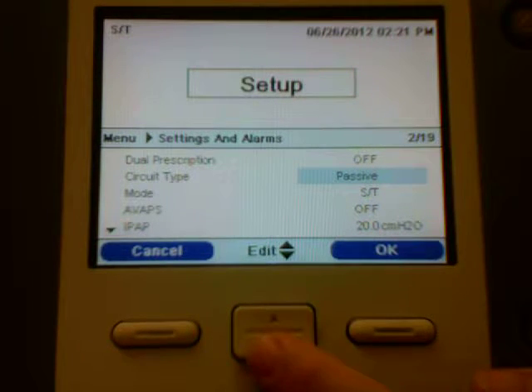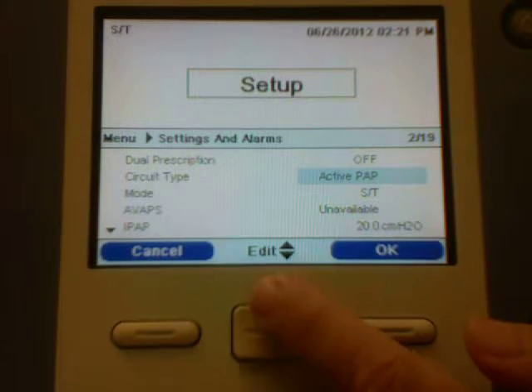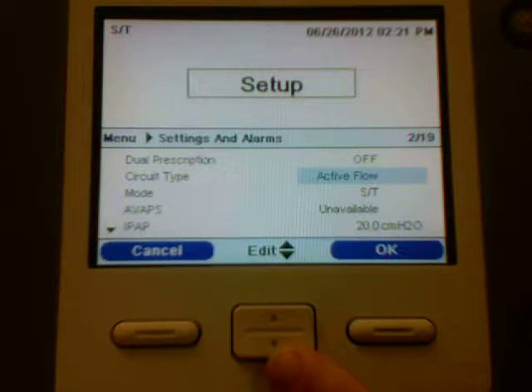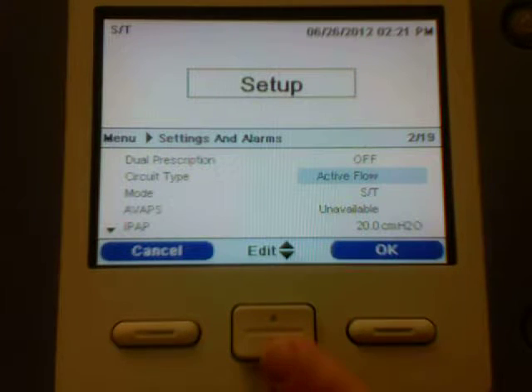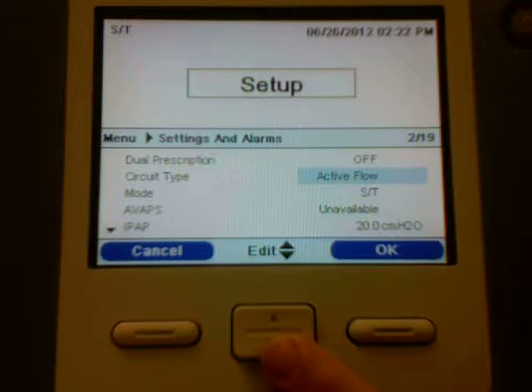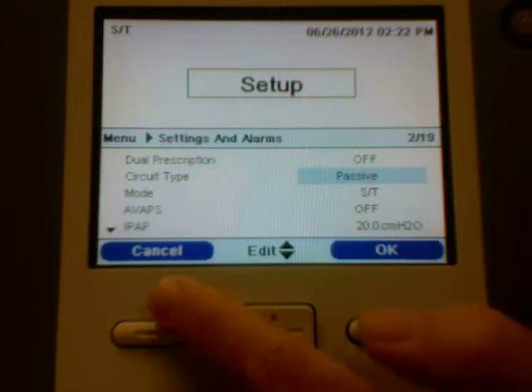And here's the types: the passive with the Whisper 2 swivel, the active circuit that has the exhalation valve built in, much like the IPPB circuit does, and then finally the active flow circuit, which is a combination of that circuit, the one with the exhalation valve, and the flow sensor in line. But for this application, let's stick with passive.